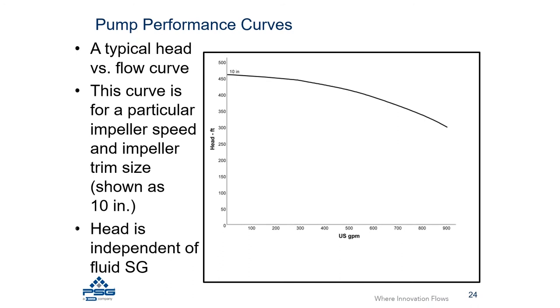The first part of a performance curve is the head versus flow line, or H-Q curve, for a centrifugal pump. The vertical axis is typically head in feet or meters, and the horizontal axis is typically flow in gallons per minute or another flow measurement. There is a line defining how much head the pump generates at a particular flow rate, and that line represents a specific impeller trim.